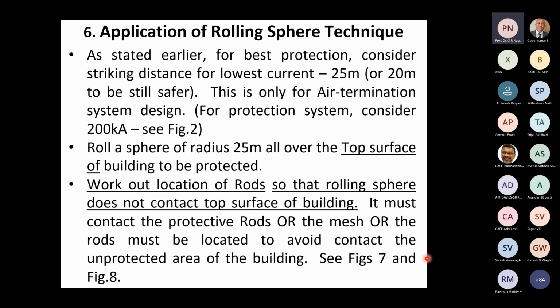The sphere is rolled on the top surface. Now, our job is to see that the protective rods, the lightning rods or the Franklin rods, must be so located that the rolling sphere touches the tips of the rods and not the top area of the building. That is how we have to choose the location of the rods. I will repeat it. Roll the rolling sphere on top of the building, and see that rods are located such that the sphere will touch the tips of the rods, but should not touch any of the areas directly.